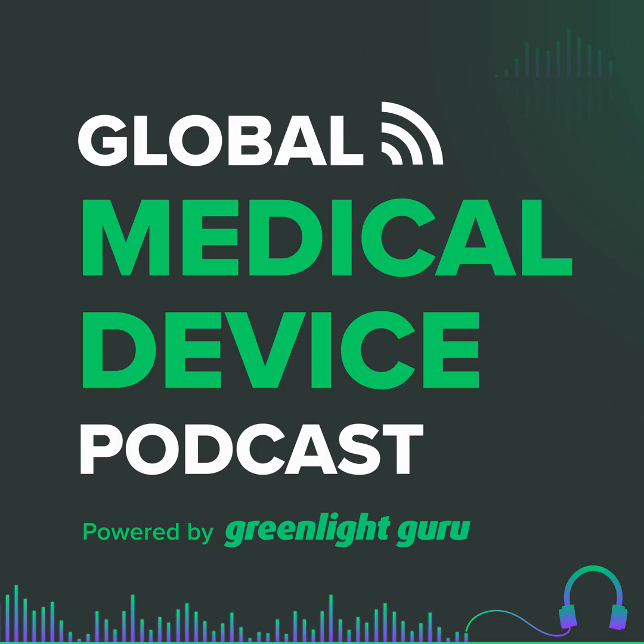So I see, and if somebody can think of one, please share it with me, no logical reason why a PCCP must be contained within a new submission. I guess the only thing I'm thinking through is that the FDA would be looking at it with fresh eyes, as if they're looking at a new submission, because they don't have the context of the original device. Of course, they'd have to go get that. Right, it's almost as if what you're suggesting is it would require the same level of rigor as a special 510(k). Yeah, it's just after the fact, as far as when the company needs it.